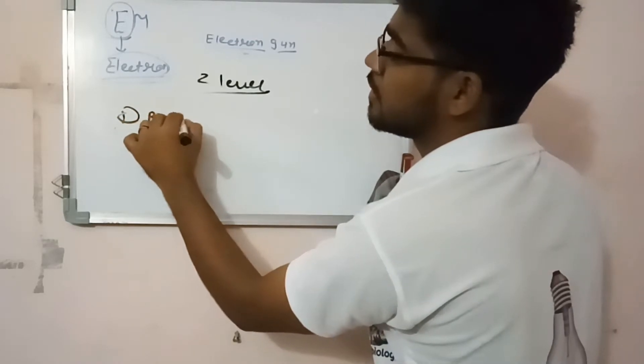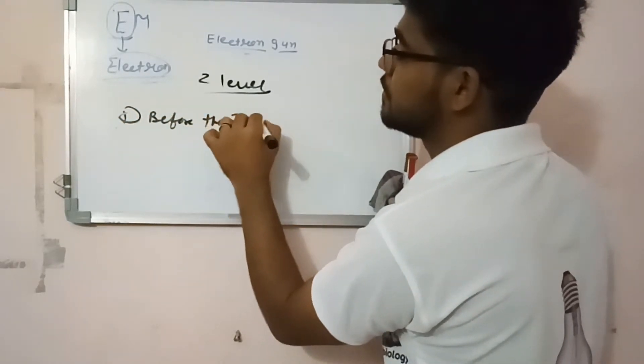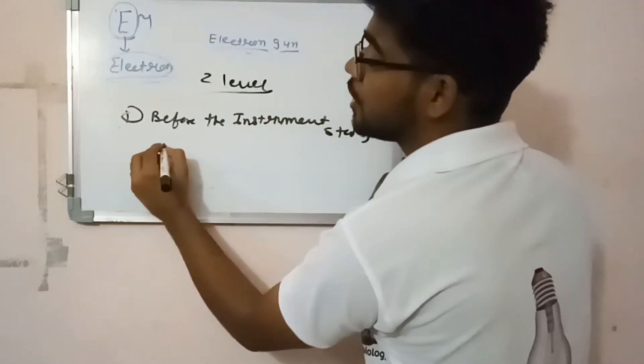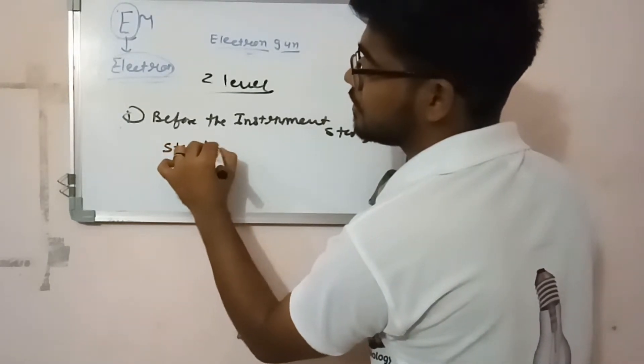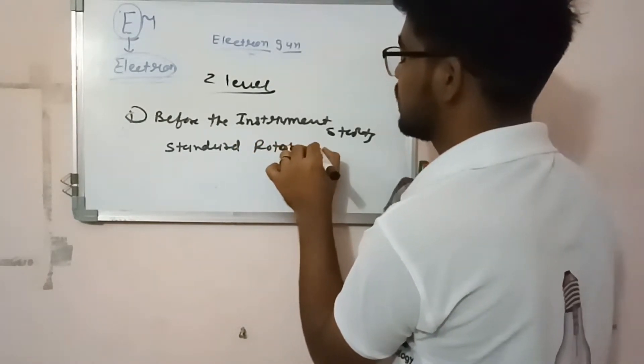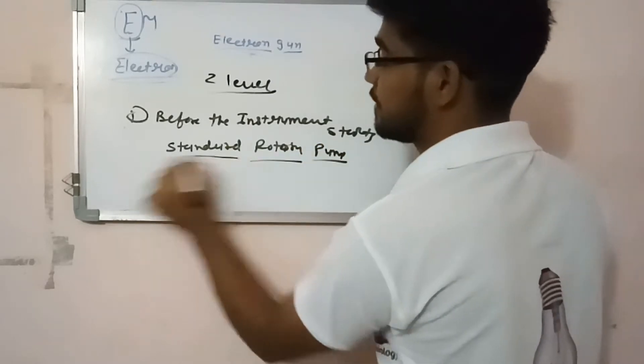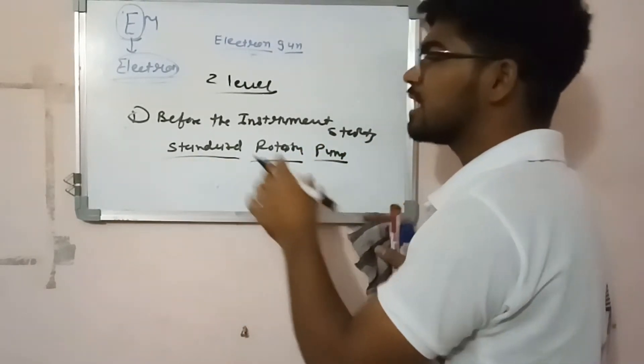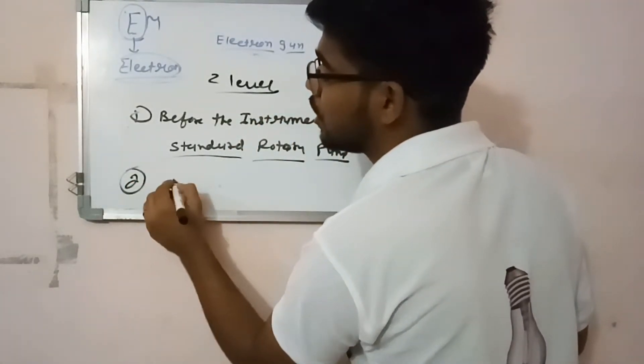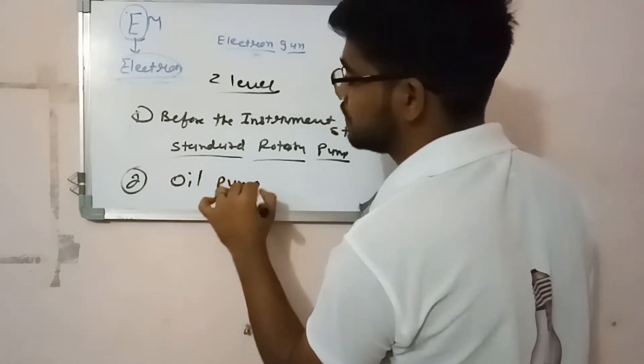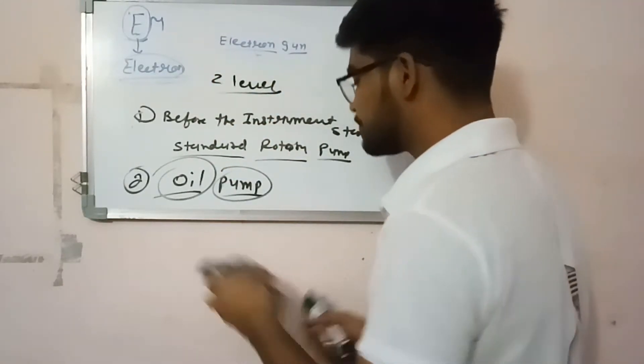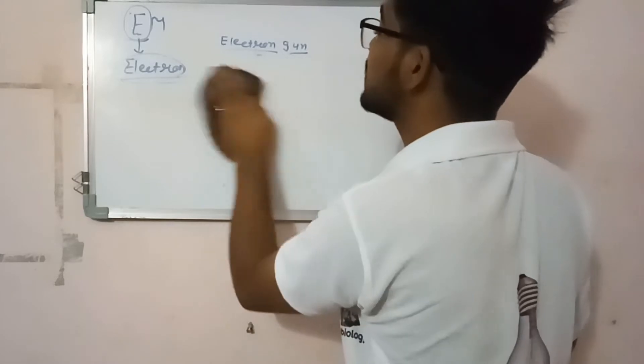Before the instrument starts, a standard rotary pump is there. The rotary pump reduces the molecules inside the instruments. At the second level, the oil pump is there. This creates vacuum near the electron gun. This is the basic instrumentation or differentiation between electron microscopy and light microscopy by instrumentation.